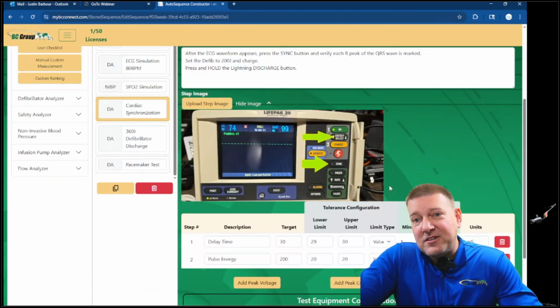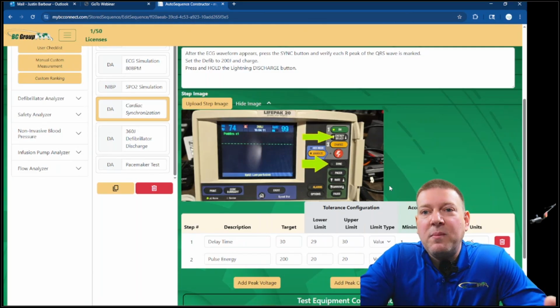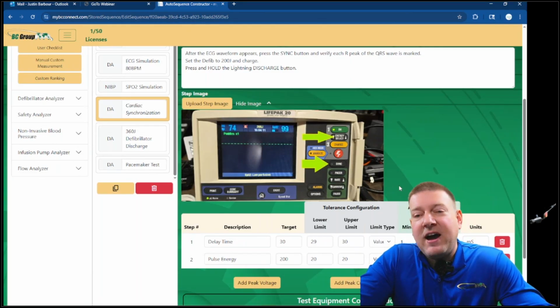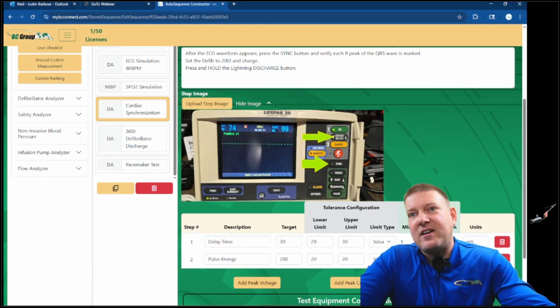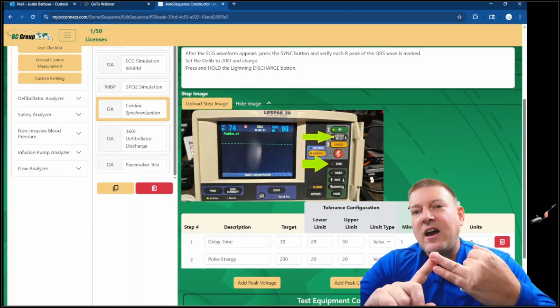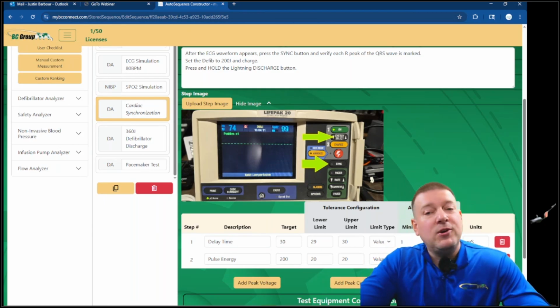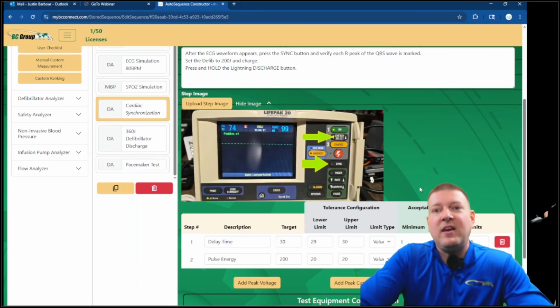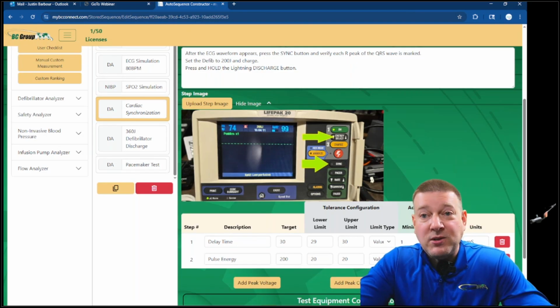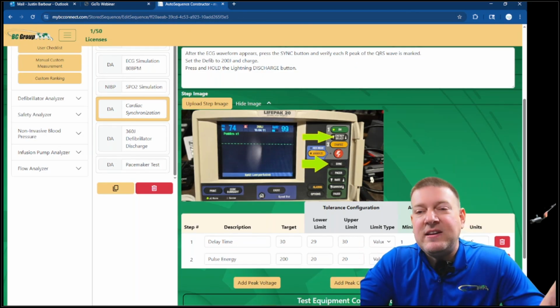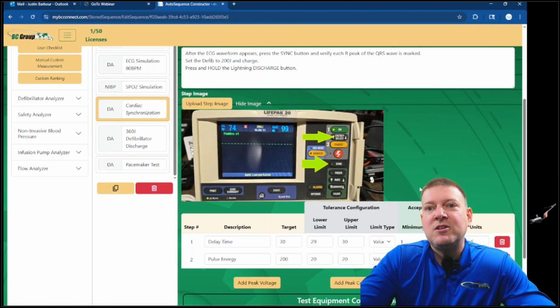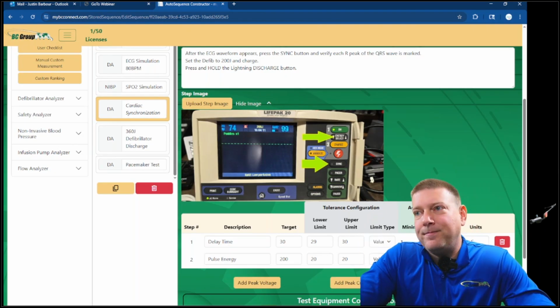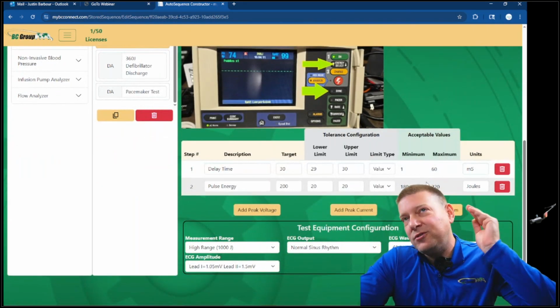Now, when you do this, the test equipment will automatically give you a pass or fail for everything on this test, for the pulse energy and for the timing. It's going to gather that. You don't have to go into separate menus or anything. It will automatically know what menu you have to be on, and it will capture that data as soon as it receives the discharge, and it gives you a pass or fail. Pretty cool. Makes this test go so much faster.